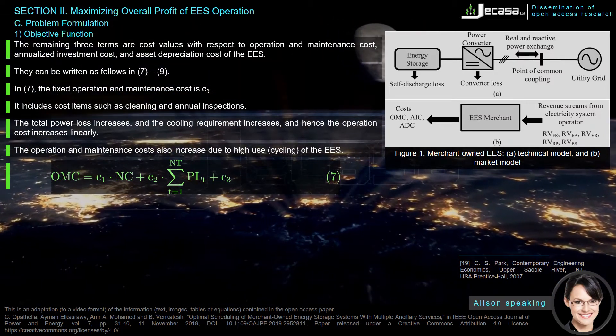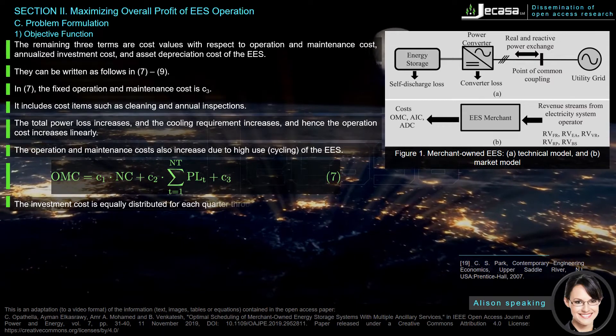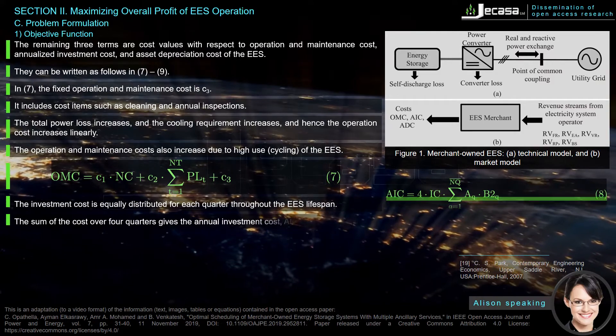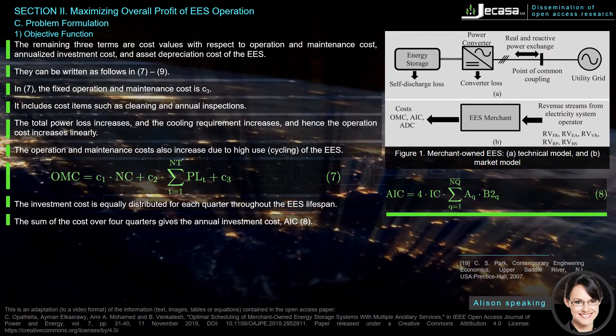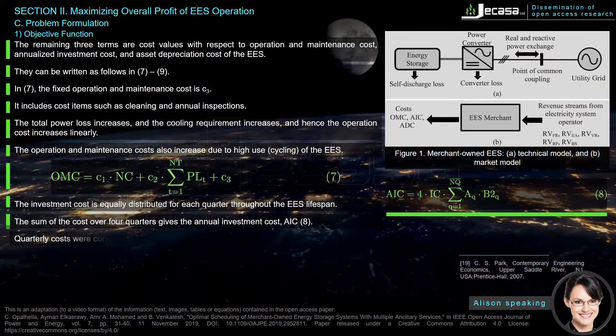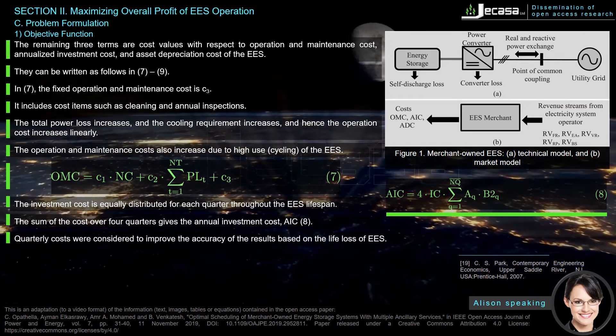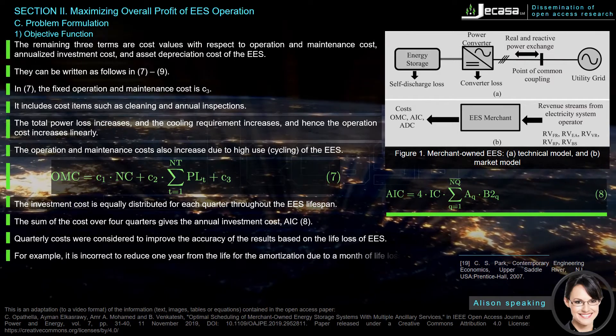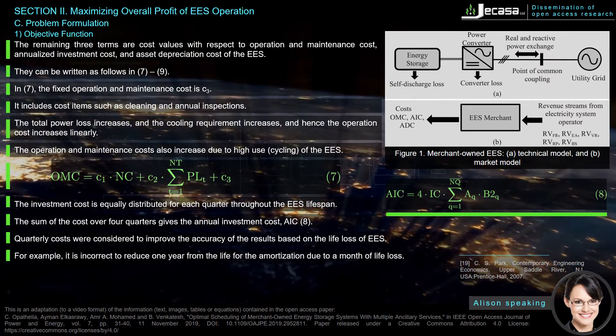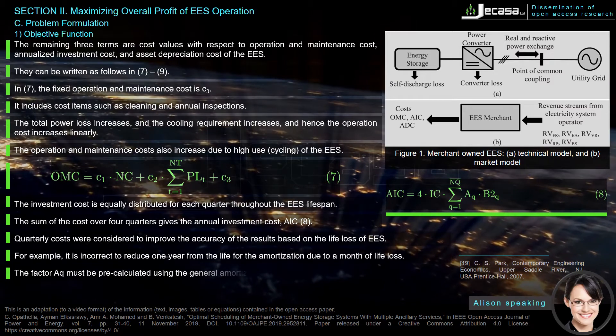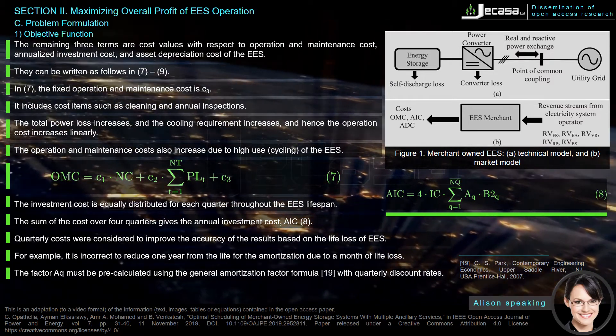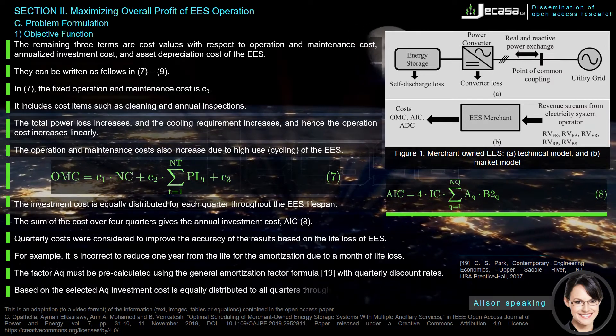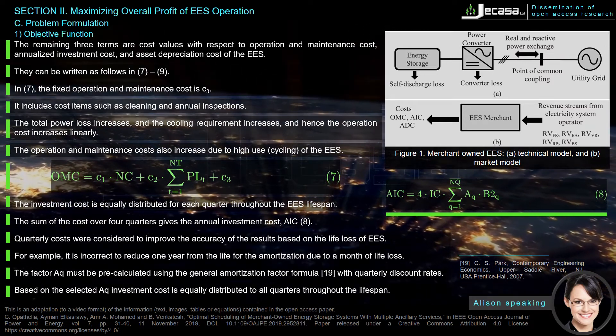The investment cost is equally distributed for each quarter throughout the EES lifespan. The sum of the cost over four quarters gives the annual investment cost AIC in equation (8). Quarterly costs were considered to improve the accuracy of the results based on the life loss of EES. For example, it is incorrect to reduce one year from the life for the amortization due to a month of life loss. The factor AQ must be pre-calculated using the general amortization factor formula with quarterly discount rates. Based on the selected AQ, investment cost is equally distributed to all quarters throughout the lifespan.